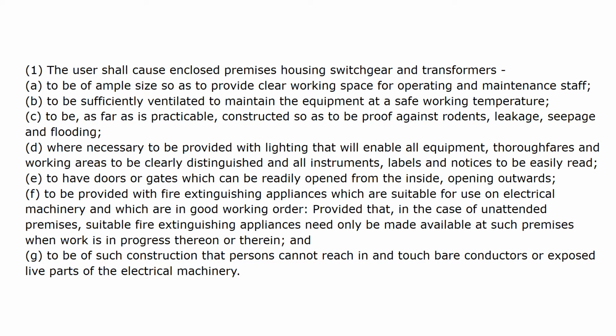D. Where necessary, to be provided with lighting that will enable all equipment, thoroughfares, and working areas to be clearly distinguished, and all instruments, labels, and notices to be easily read. E. To have doors or gates which can readily be opened from the inside, opening outwards. F. To be provided with fire extinguishing appliances which are suitable for use on electric machinery and which are in good working order, provided that, in the case of unattended premises, suitable fire extinguishing appliances need only be made available at such premises when work is in progress thereon or therein, and G. To be of such construction that persons cannot reach in and touch bare conductors or exposed live parts of the electrical machinery.